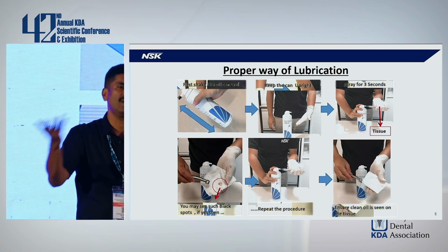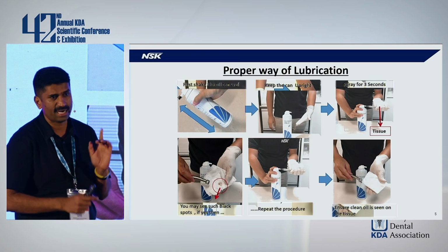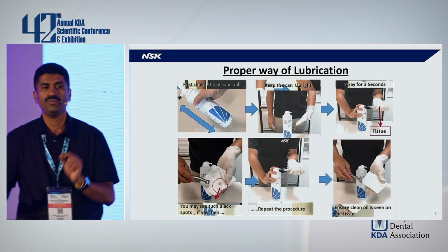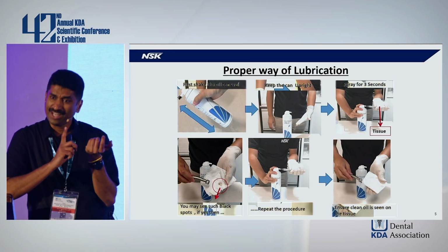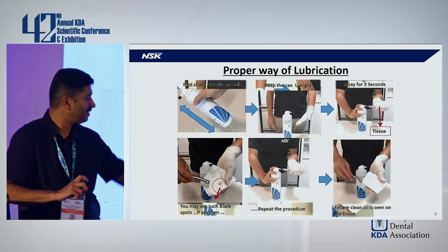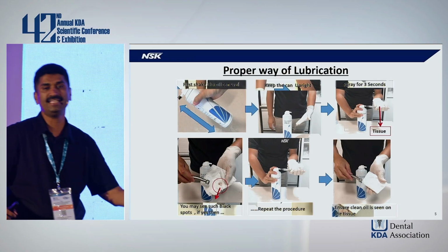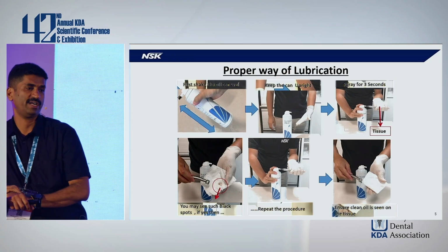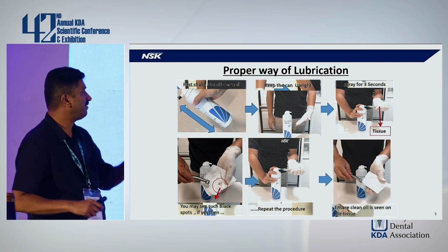So you can autoclave after every operation, or you can autoclave once a week or once a day. But whenever you autoclave, we recommend you do an additional lubrication before autoclaving in the same fashion, and then put the handpiece into the autoclave. Now, what is the reason we have to lubricate before autoclaving?